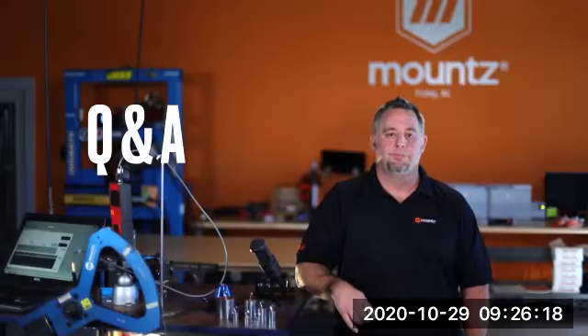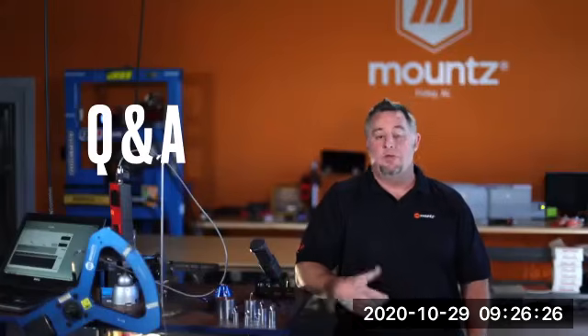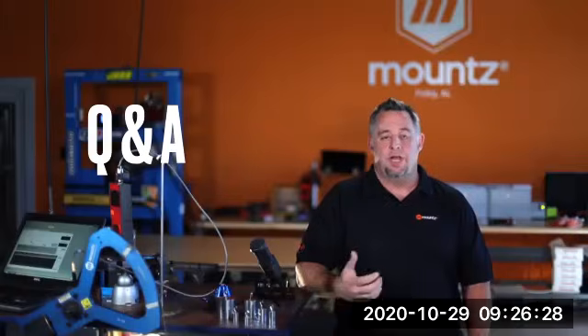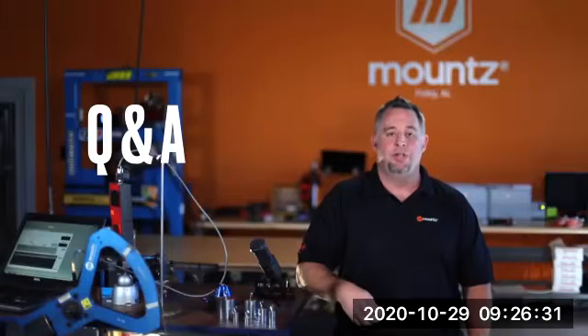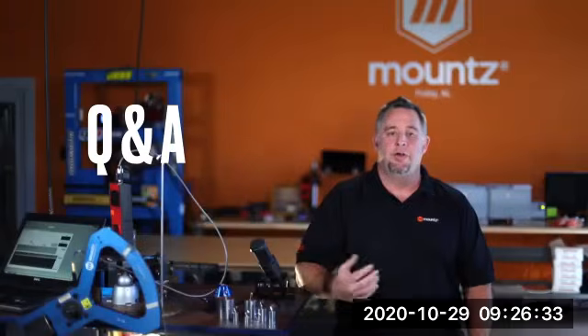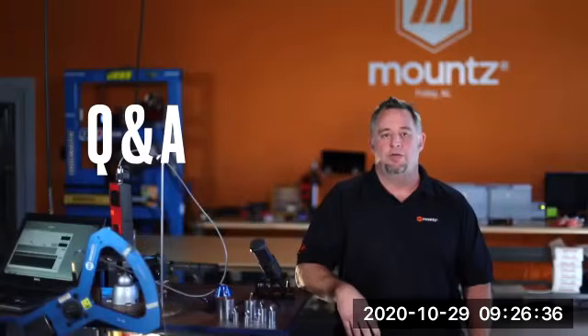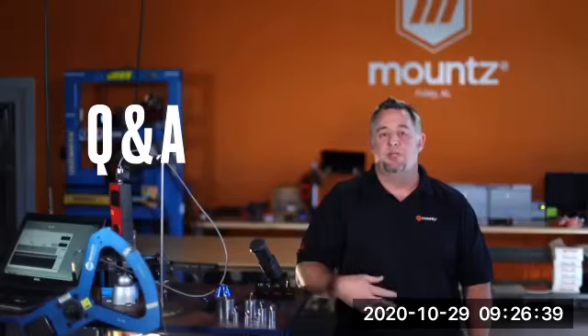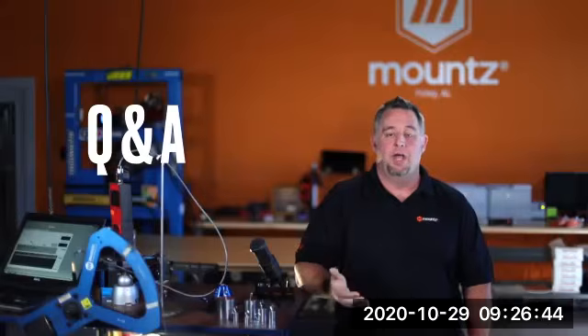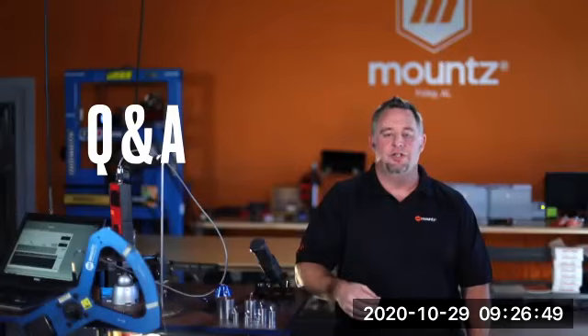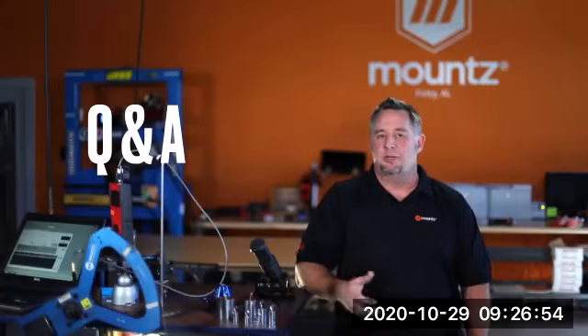Can the Mountz transducer calibration due date be updated in the field, and if so, how? If you have the software, you can go in and change the calibration date. That is part of the software, but it is password protected, so it's not something that can be done by accident. You'd have to have the intention of actually changing the date to do that, but it is possible. Again, it's password protected.